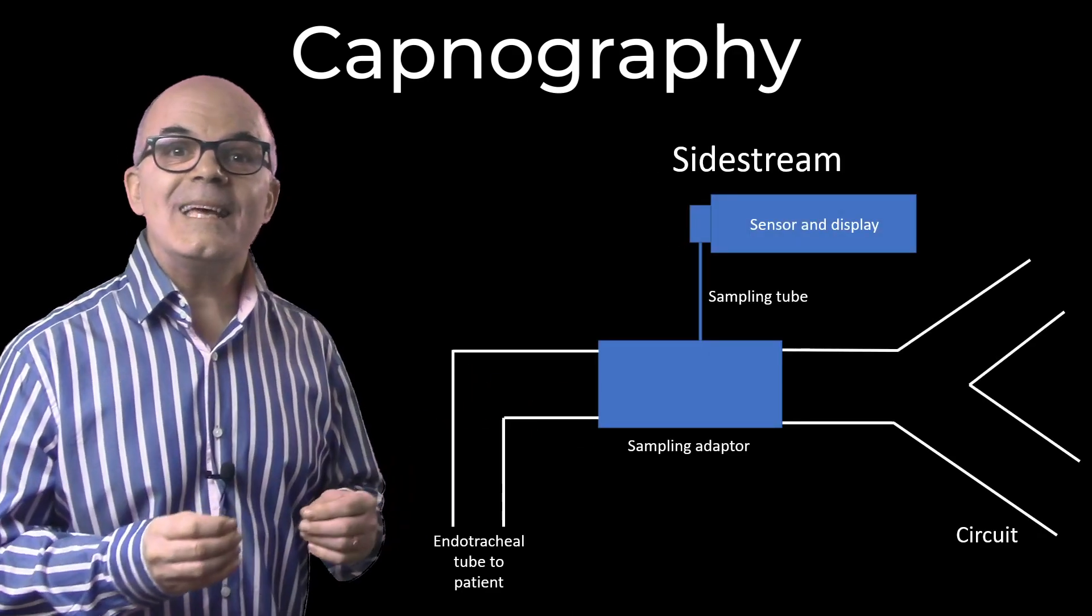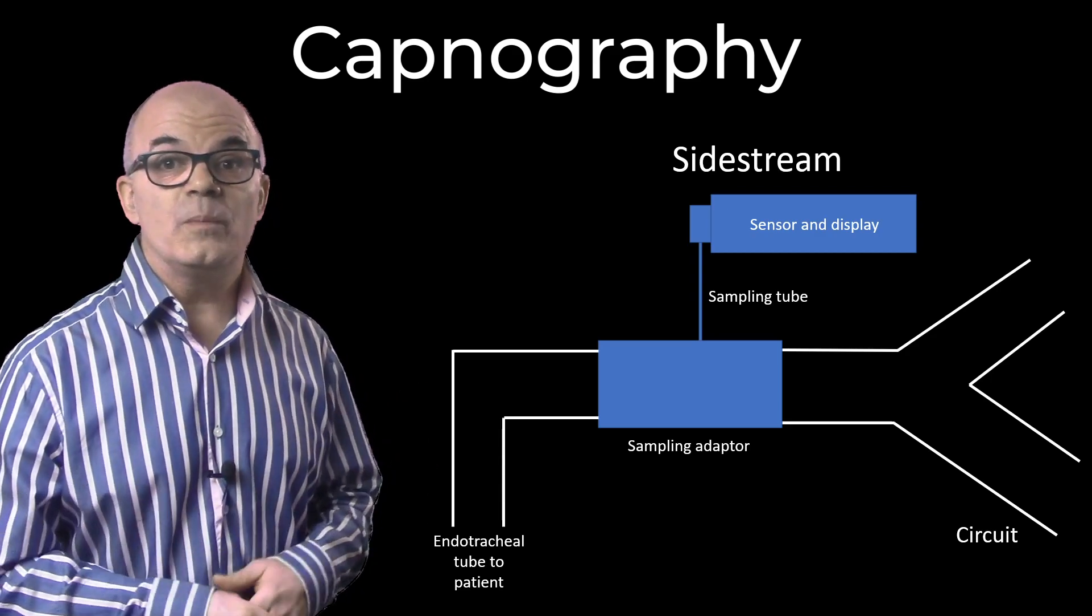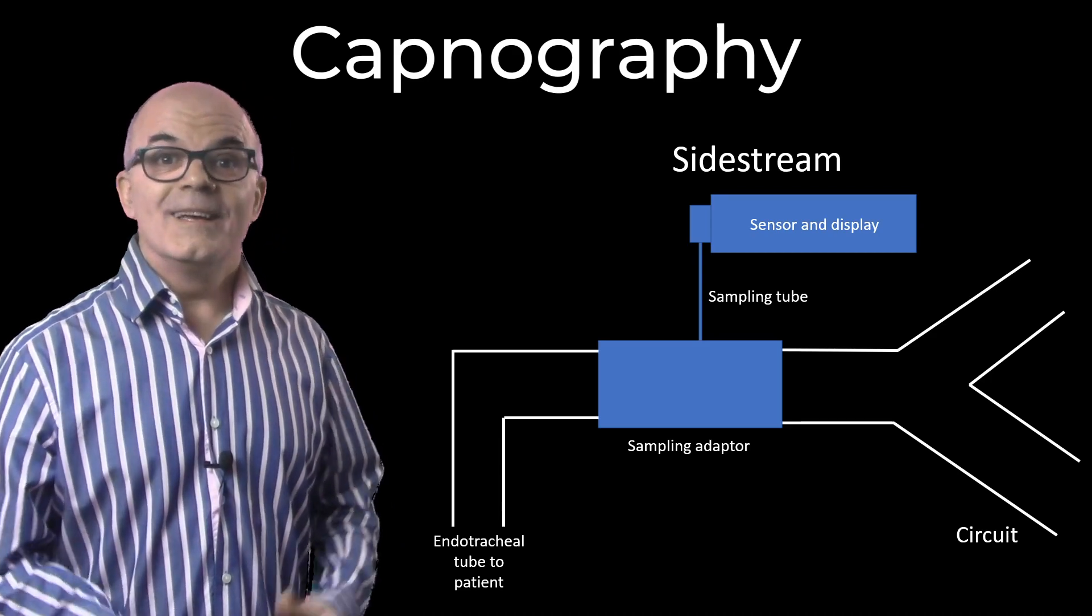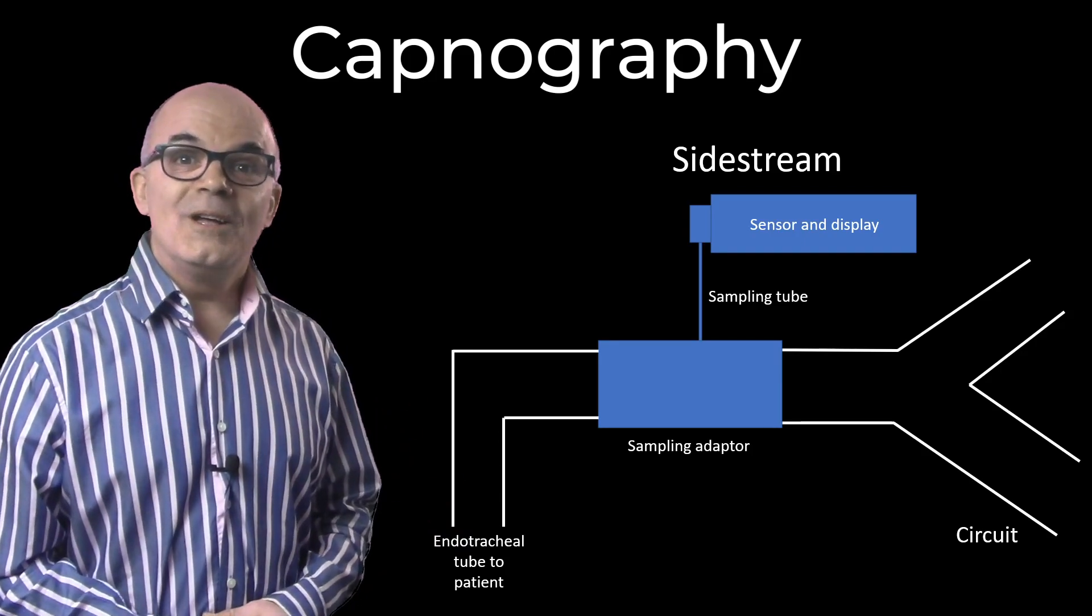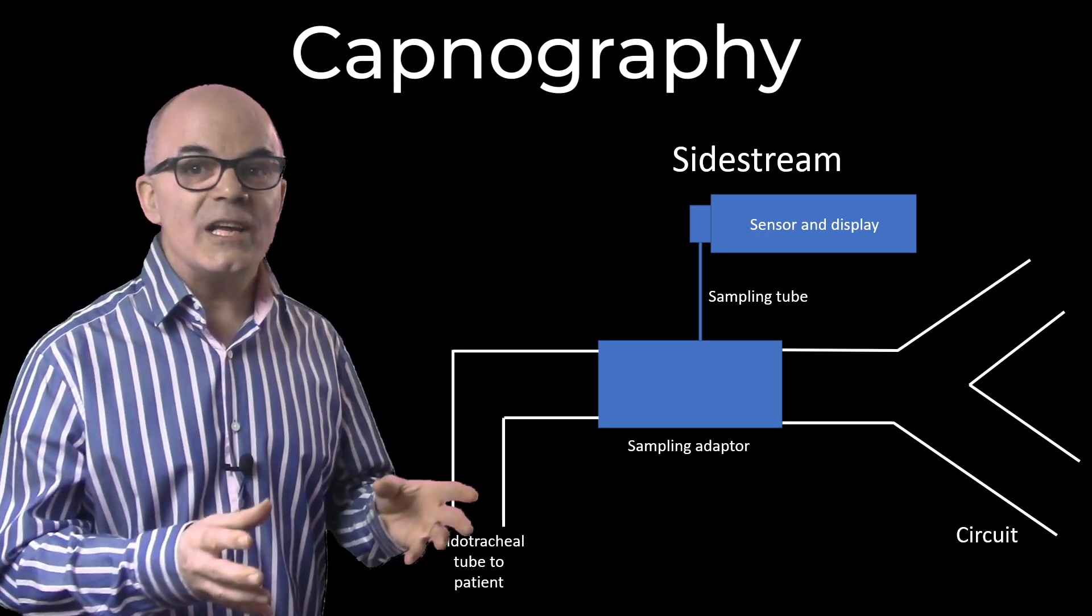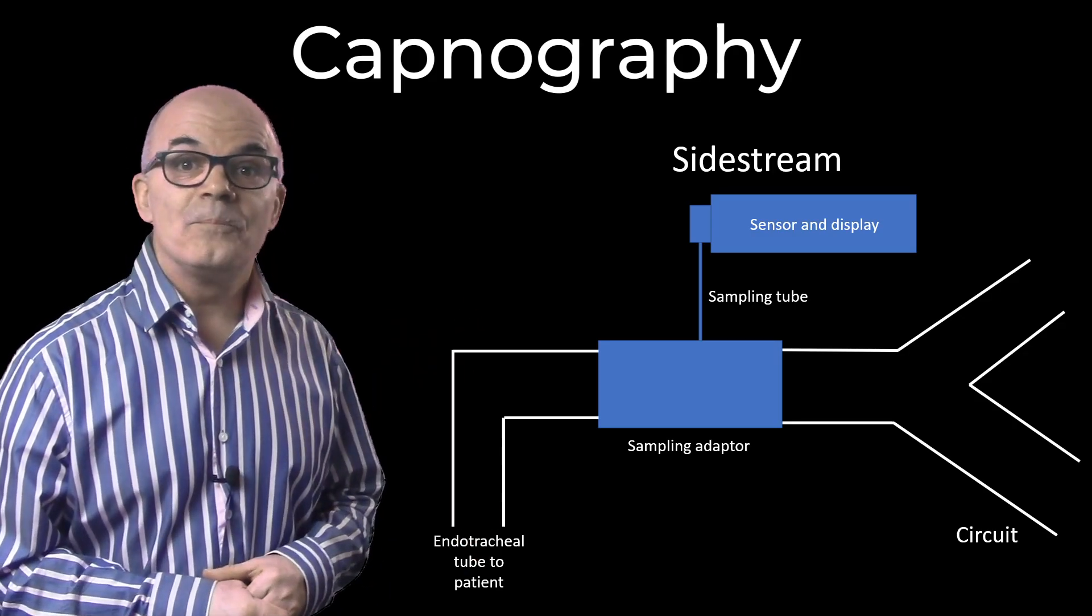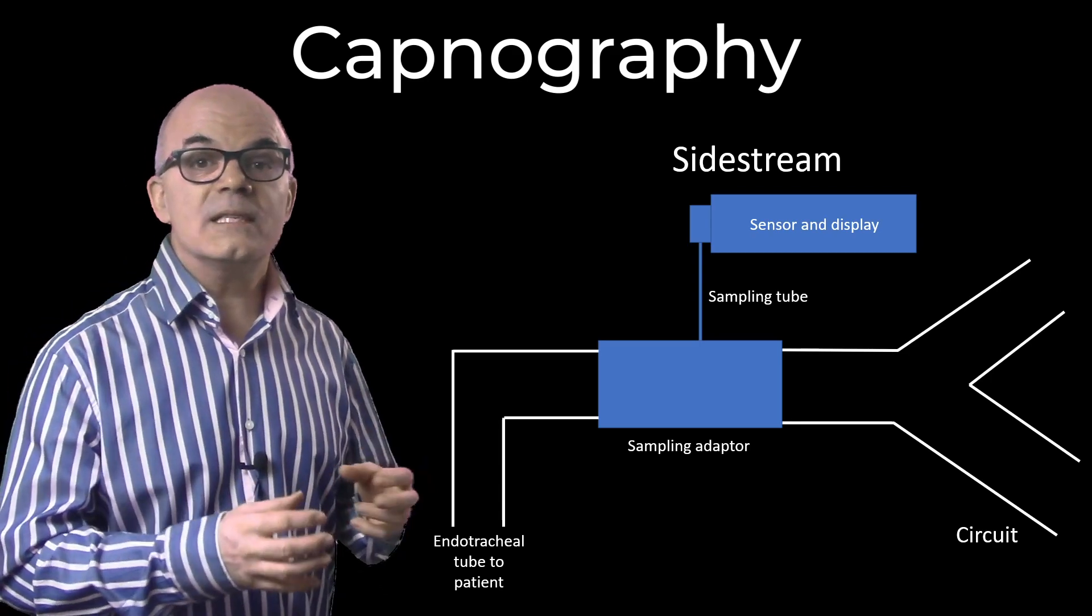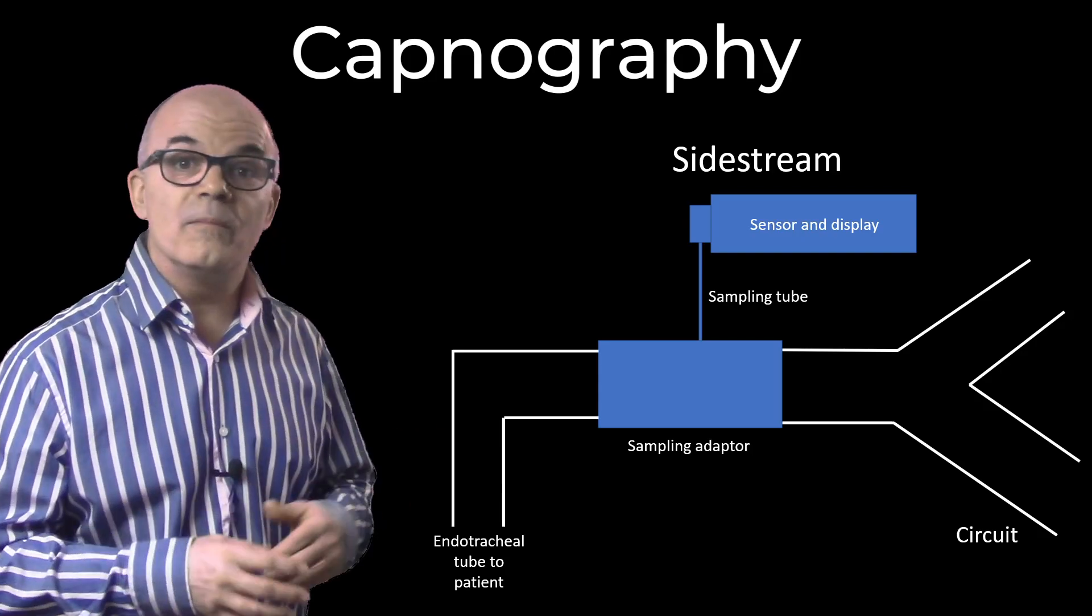Sidestream. The detector is now remote from the patient and attached to a short piece of tubing, which is then connected to the endotracheal tube via capillary tube. The gas is then taken to the detector via this capillary tube. Although less bulky than the mainstream, it does mean a slight delay between changes in the patient's expired CO2 and this being reflected on the monitor. They also include the need for a suction pump to draw the sample into the measurement chamber, and there can be inaccuracies caused by suction pump function.